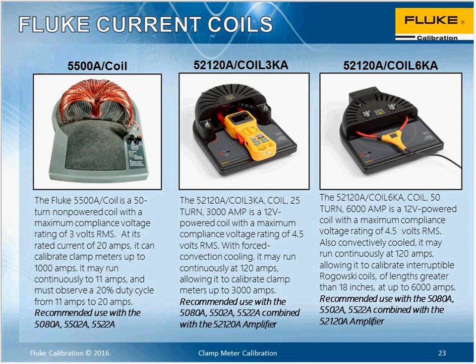Fluke offers 3 different types of coils that work very well with the multi-product calibrators. The one on the left goes out to 1,000 amps, and it does have a time limit with a 20% duty cycle, but that should be plenty of time if you're running an automated procedure, or even a manual procedure, to get a stable measurement.